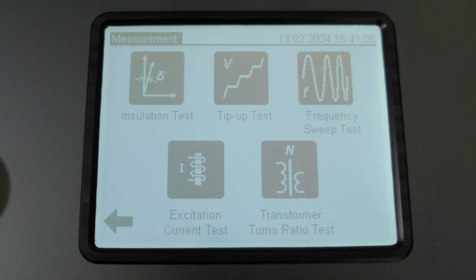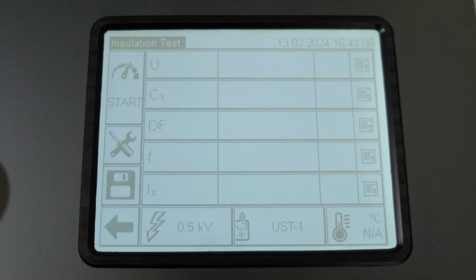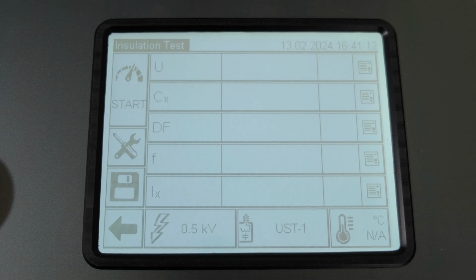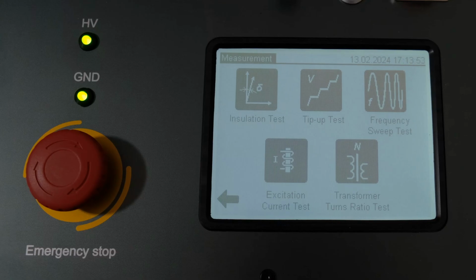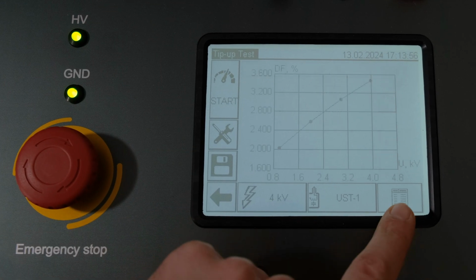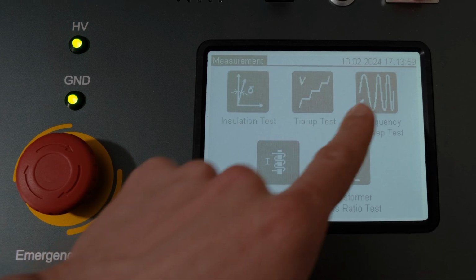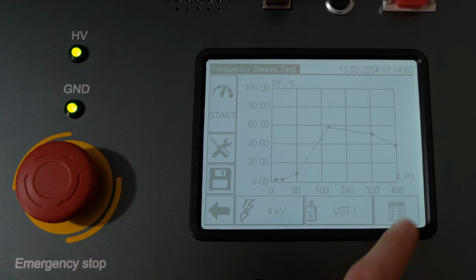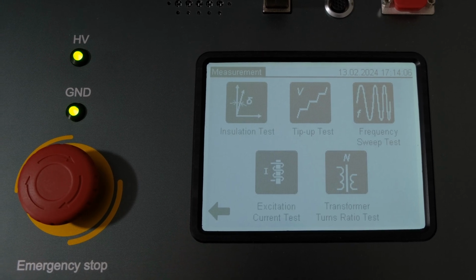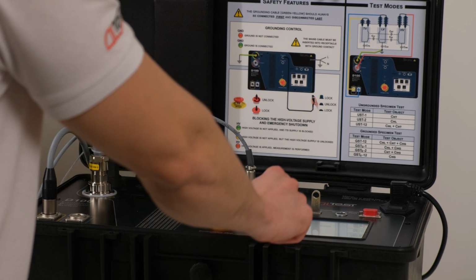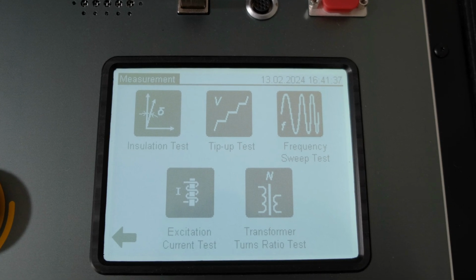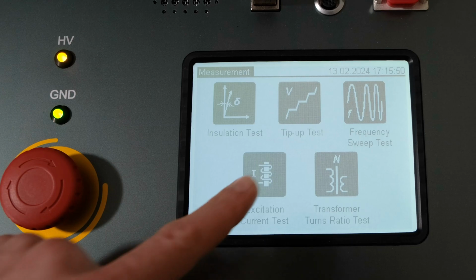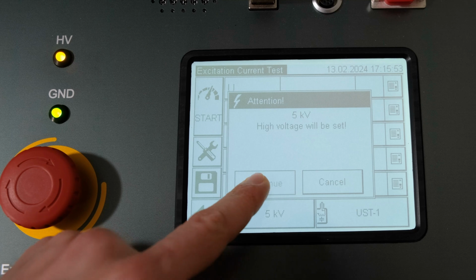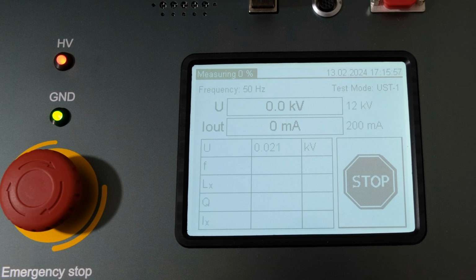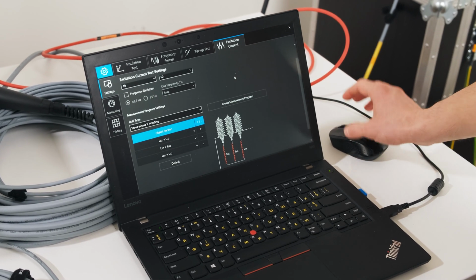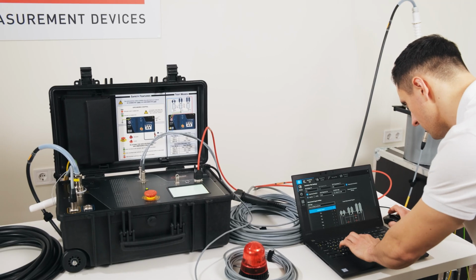D100 takes measurements in the following modes: insulation test, in which the capacitance of the tested insulation section is measured, and tan delta or power factor. Tip-up test is intended to determine the dependence of the tan delta or power factor on the applied voltage. Frequency sweep test is intended to determine the dependence of the tan delta or power factor on frequency at a test voltage from 100 volts to 4 kV in the frequency range from 15 to 400 Hz. The excitation current test is intended to measure the no-load current and inductance. The transformer turns ratio test is intended to measure the transformer turns ratio for single-phase excitation.